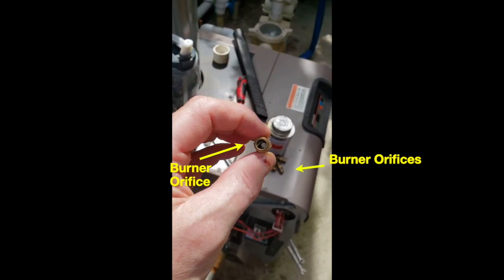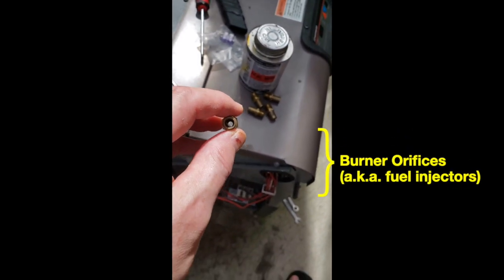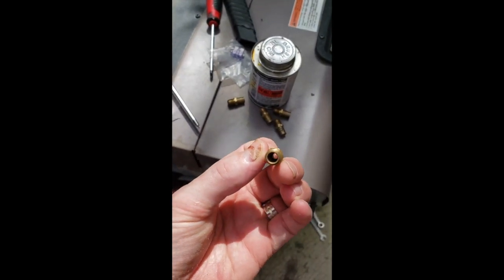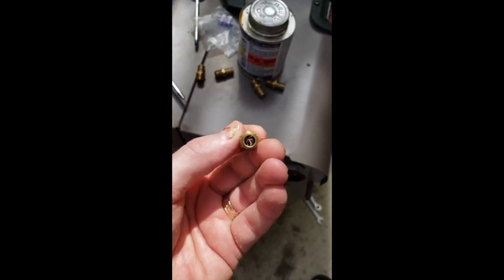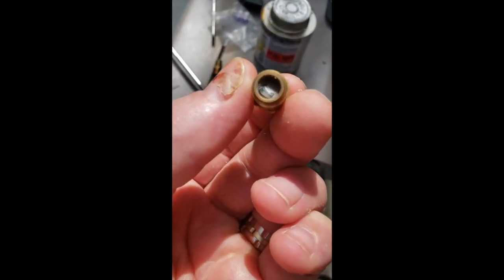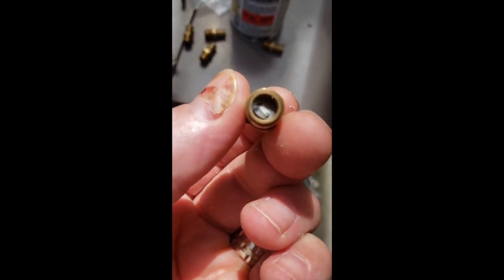Taking each of the pieces off — they all come out of the manifold down here. I've taken each one off. Four of the five orifices have cobwebs inside of them. This one is nice and clean, but you can see the others have gunk inside. Cobwebs — and what people are saying online is that spiders really like getting inside these things.